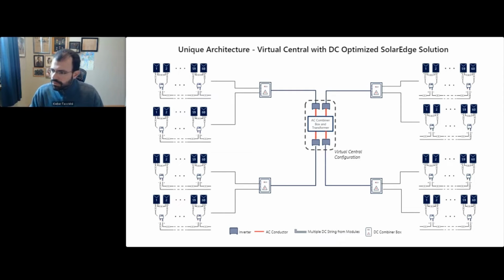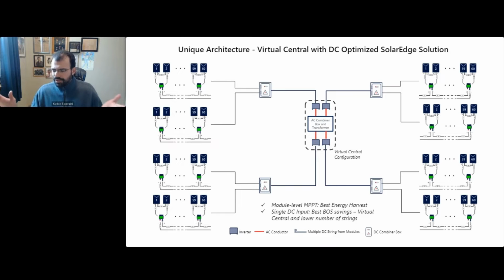The use of this optimization allows for even longer strings when compared to conventional 1500 volt DC string inverters, as well as the flexibility to use strings of different lengths. It is worth saying it again, the solution enables up to 80 modules connected per string, and energy is harvested at the module level. Longer strings of modules translate into fewer strings per inverter, which means fewer disconnects, fuses, and overall savings on DC cable.